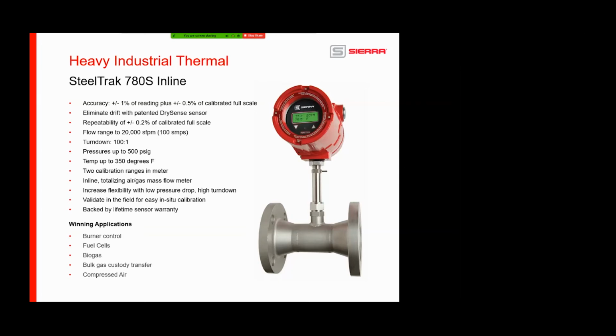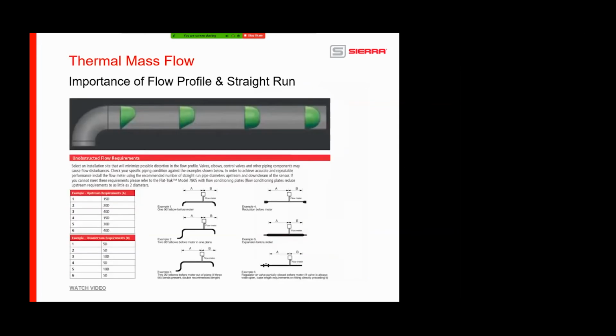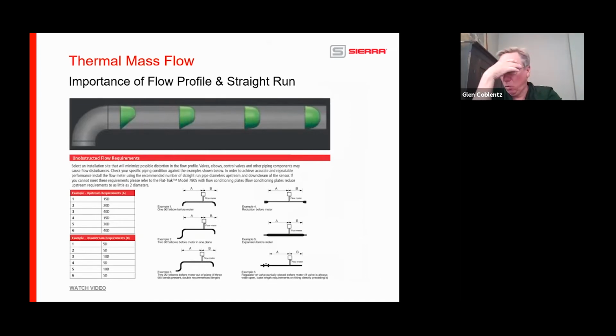Glenn, a couple quick questions. First, got a question about the USB on the 640i, 780i. When is that going to be going live? And we can move away from the RS-232. Great question. So for those of you that have worked with the 241i and the 240i in the field, that's our mass vortex meter. If you've done that, you've noticed that the USB on there works. Plug it into the laptop with the USB. I always recommend that you get a separate isolation protector because sometimes the customers don't quite have electrical wiring down and there's a lot of voltage that sits on that meter. And guess what? As soon as you plug in a USB to a USB laptop with no protection, all that voltage goes to your laptop and guess what? Pop. Laptop no longer works.